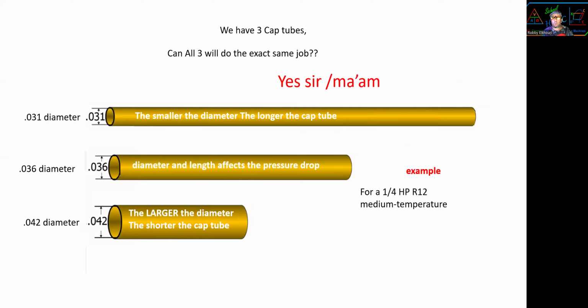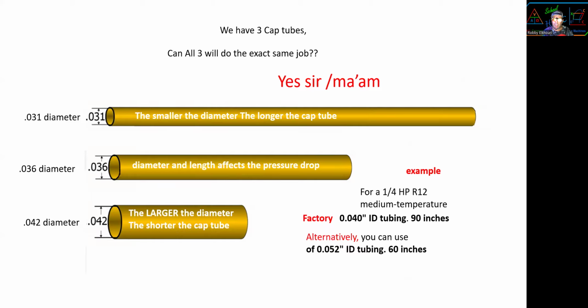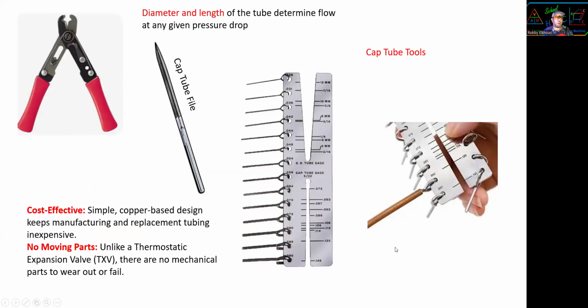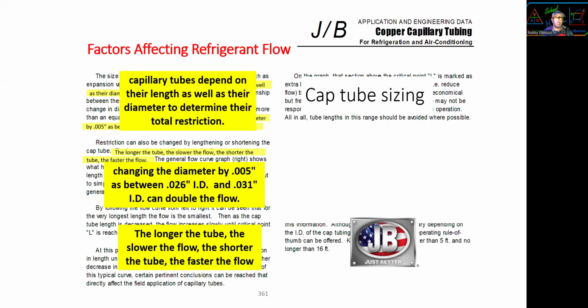Example, for a quarter horse R12, medium temp. So the boiling point should be about 15 to 20 for medium temp, correct? Yep. Factory, 0.04 inch ID, 90 inch long. We can use 0.052 ID and 60 inch long instead, because the chart will tell us. These are tools for the cap tube. Cap tube sizing depends on the length as well as the diameter. Changing the diameter of the ID can double the flow. The longer the tube, the slower the flow. The shorter the tube, the faster the flow.